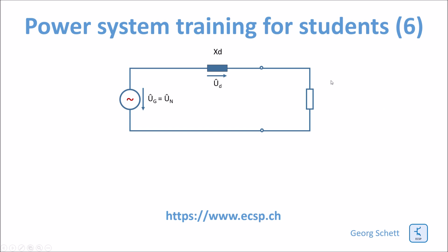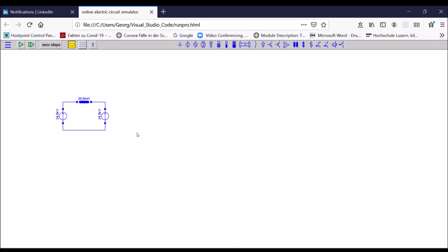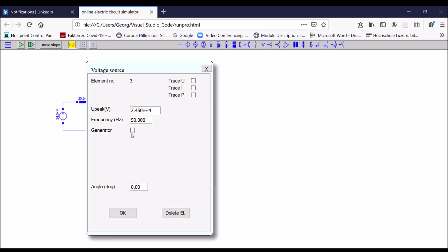Now I want to see what happens if I replace my load — my resistance — by an infinitely stiff bus, a stiff grid. The stiff grid does two things: first, the frequency is 50 Hz and will stay there independently of what the generator supplies; second, it also delivers the nominal voltage independently of the voltage of the generator. My generator still operates in generation mode with a droop and a nominal power output of 100 MW per phase.